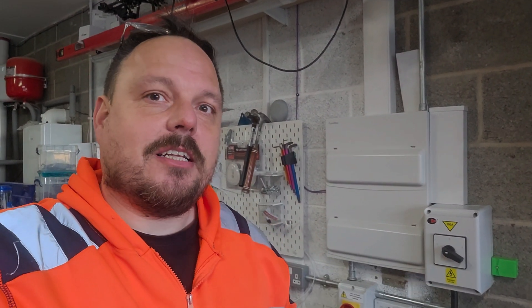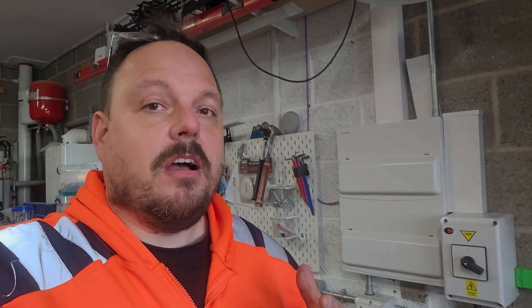Hello and welcome back to the channel. It is Mark from PowerSonic and Apprentice One-to-One. You will see behind me we have added a manual changeover switch to this installation. This is one we swapped the fuse box on two, maybe three years ago now, and the customer has had an upgraded inverter, battery storage, and they're wanting to add the function of being able to run the property off-grid.